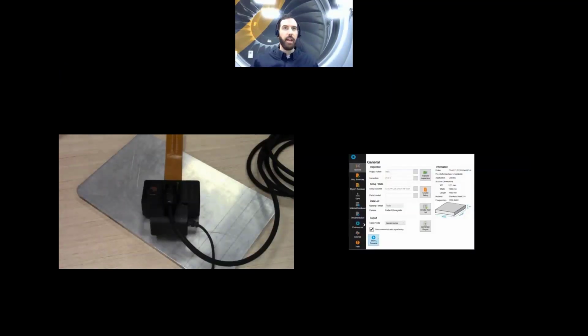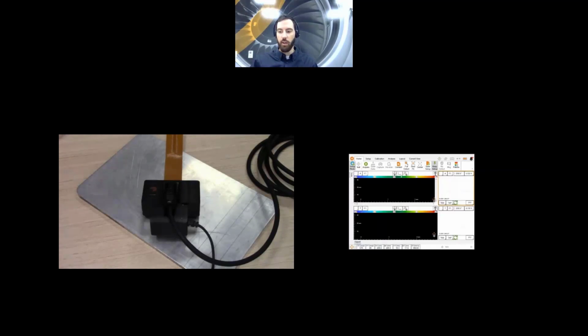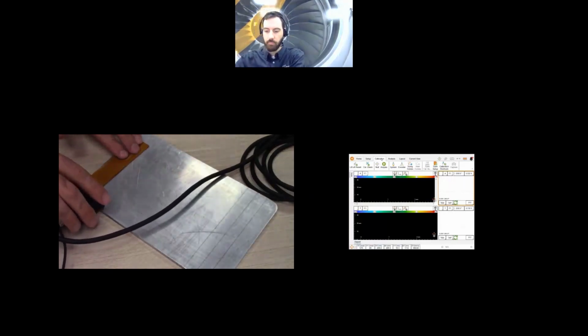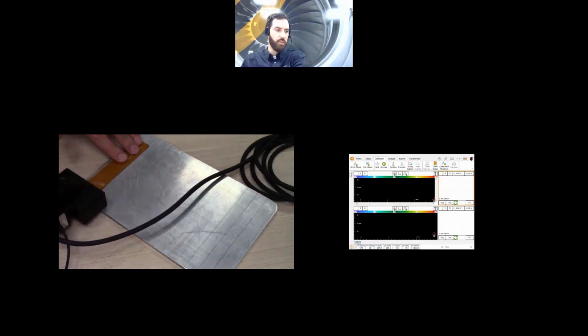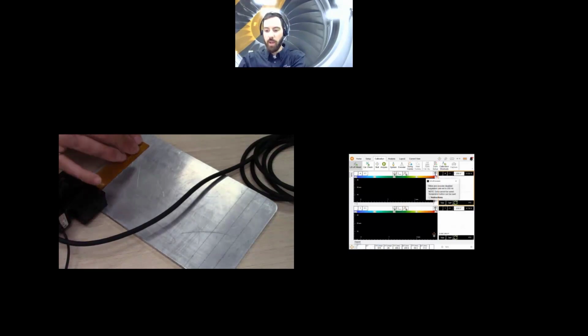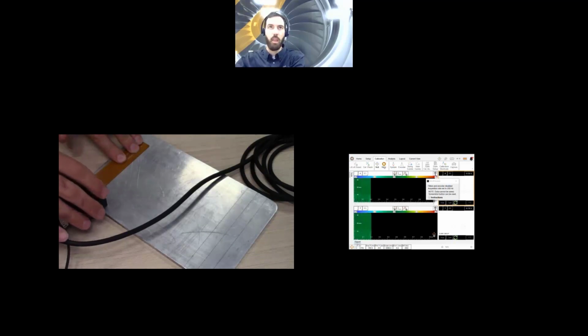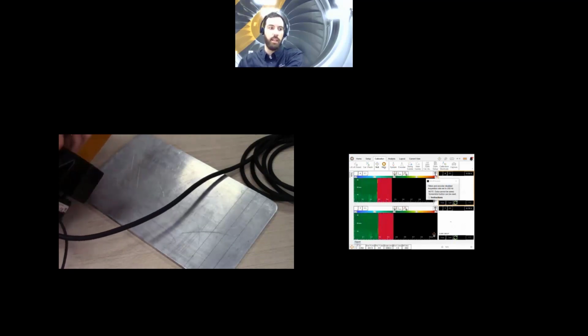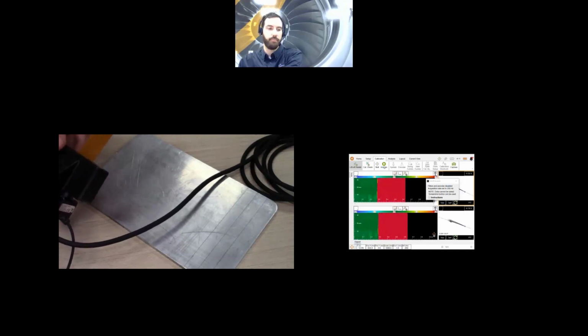Going back to Magnify, I will move to the front stage, and the first thing I will be doing here is a liftoff calibration. So I go to the Calibration tab, Liftoff Assistant. I make sure my probe is in contact at a clean location of my plate. I will null the probe there and acquire data. Now I'm simply doing a liftoff curve like that.